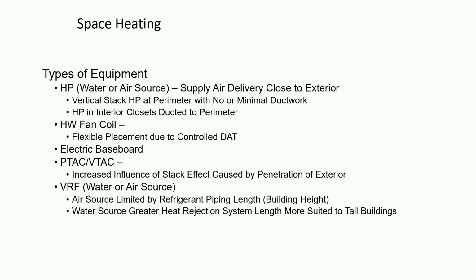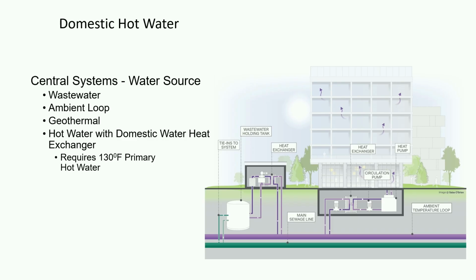For tall buildings, VRF's probably not really much of a choice. It's just too much mechanical space that you would be required to run all your refrigerant lines and put all your condensing units. So it's generally either in-suite heat pumps or fan coils, okay? And then domestic hot water.